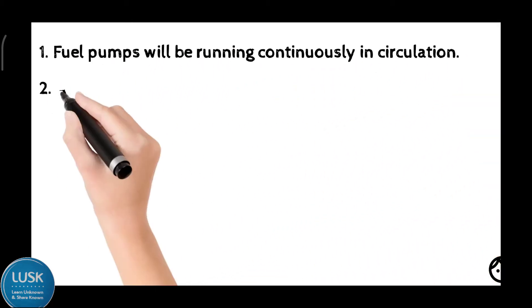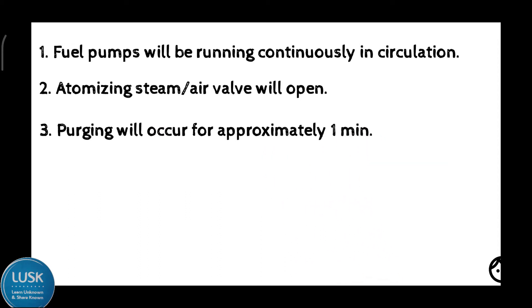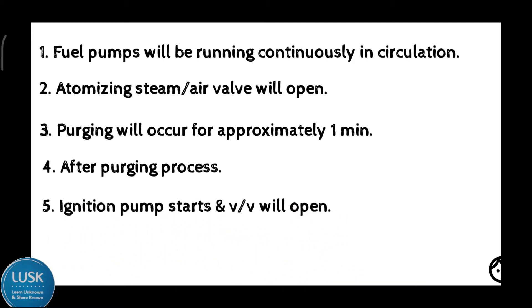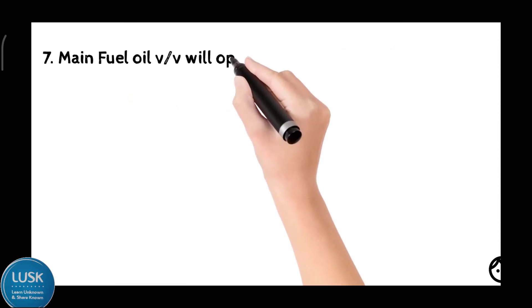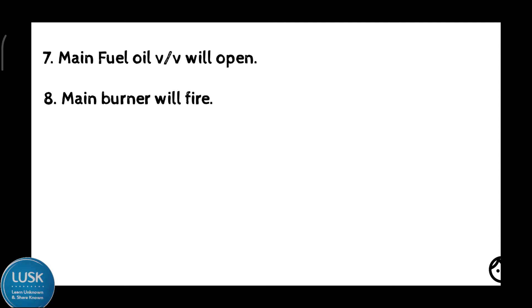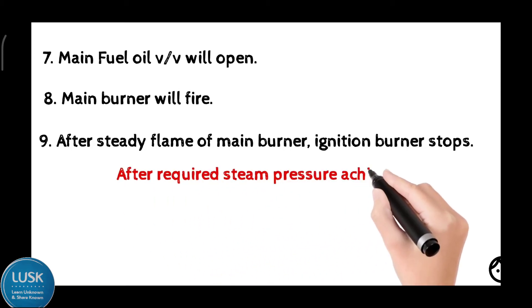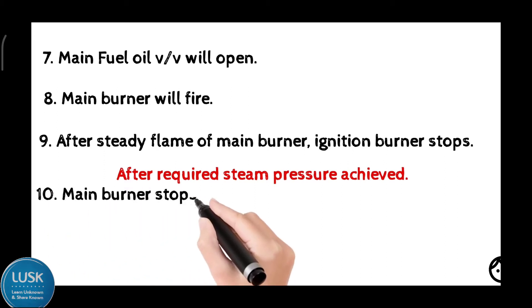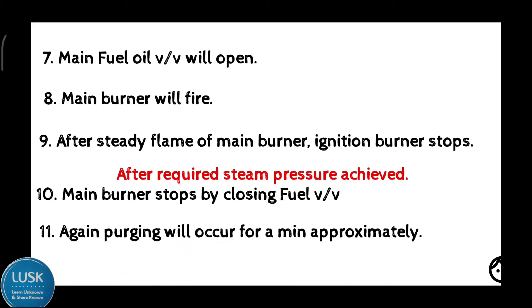First, fuel oil pumps will be running continuously. Then the atomizing steam valve will open, or compressed air valve will open for atomizing. Then purging will happen for one minute. After purging period completes, ignition burner pump will start and those two valves will open. Then pilot burner will start firing. There will be a flame sensor that will detect the flame inside the burner. Then main fuel oil valve will open, and main burner will start firing because of the pilot burner. The flame sensor will detect a steady flame. Then ignition burner will stop. After achieving the required steam pressure, main burner will stop by closing the fuel valve, and purging will occur.